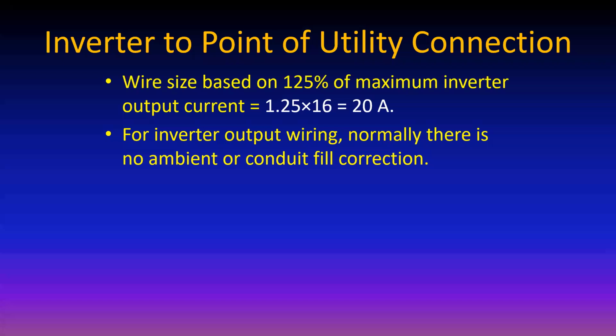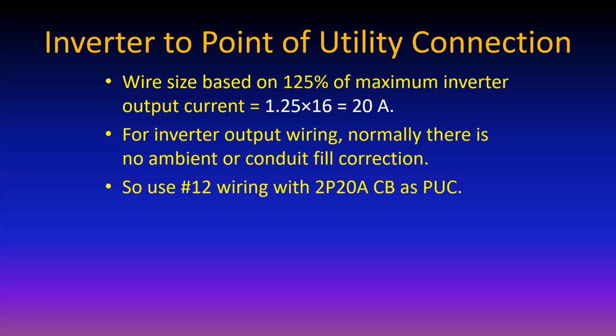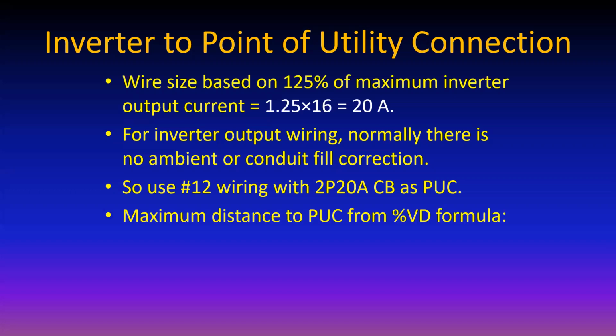So for the inverter output wiring, normally there's no ambient or conduit fill correction. Sometimes folks here are using a 0.96 conduit fill, though there's only 2 current carrying conductors, so therefore you're at 100%, and 96% or 0.96 if you're up over certain temperature for wire sizing. And it all depends on where that piece of conduit is, whether you do the 0.96 derate. So in this case, number 12 at the output to a 2-pole 20 amp circuit breaker is probably good. You can check the distance.